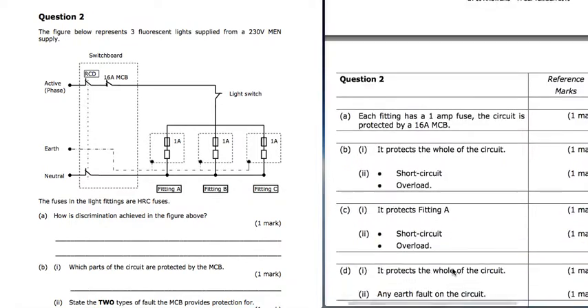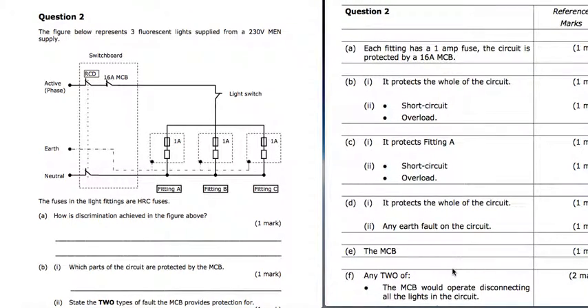And this question 2 is quite a weird question, and the answers seem very basic, but go along with it. So we've got 3 fluorescent lights here, each protected by their own 1 amp fuse, 16 amp MCB and an RCD protected. So it says, how is discrimination achieved in the figure above? Well, discrimination is achieved because we've got a lower fuse at the fitting and a higher rating MCB protecting all of those fuses. So their answer, each fitting has a 1 amp fuse, the circuit is protected by 16 amp MCB.